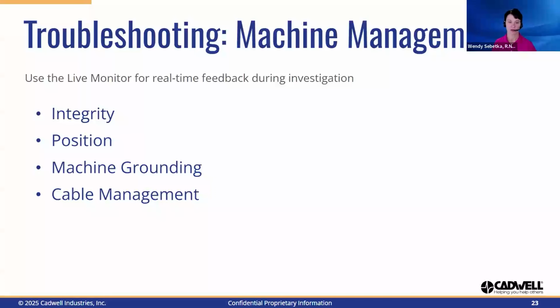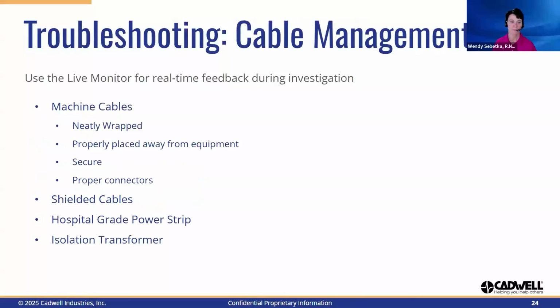Properly installed ground wires will allow excessive signals a place to go. All cables should be connected securely with appropriate connecting devices and neatly wrapped. The power cable should be directed away from the equipment rather than being wrapped around near the base unit or amplifier. When necessary, shielded cables, hospital-grade power strips, and isolation transformers may be successfully installed to help reduce the noise coming into the device.